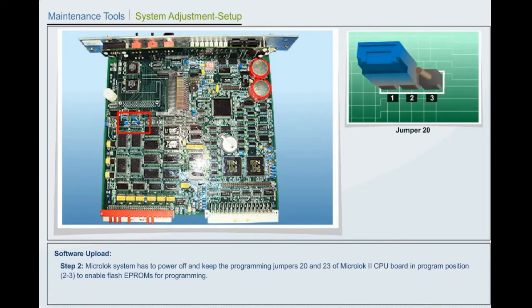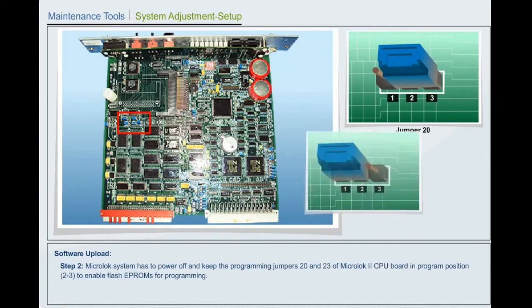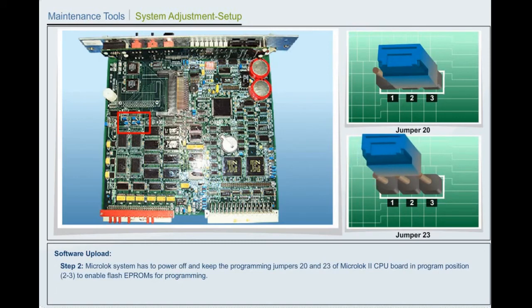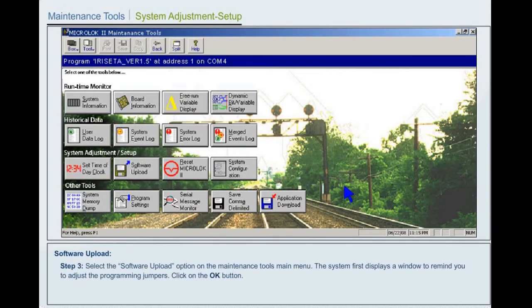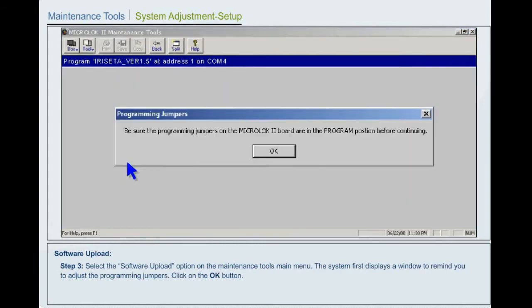Step 2. Microlok system has to power off and keep the programming jumpers 20 and 23 of Microlok II Central Processing Unit Board in program position 2 to 3 to enable flash erasable programmable read-only memory for programming. Step 3. Select the Software Upload option on the Maintenance Tools main menu. The system first displays a window to remind you to adjust the programming jumpers. Click on the OK button.